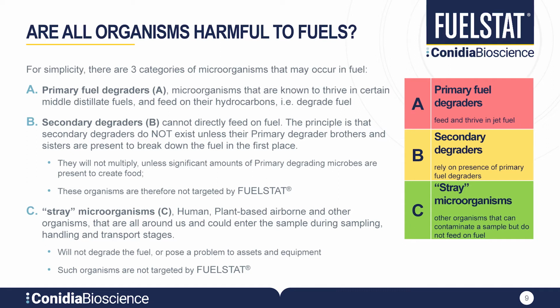A, we have the primary fuel degraders, those that actively eat the fuel, causing damage and allowing other organisms to join the party. B, we've got the secondary degraders, which cannot directly degrade the fuel and actually would not exist without the presence of their better adapted brothers and sisters.